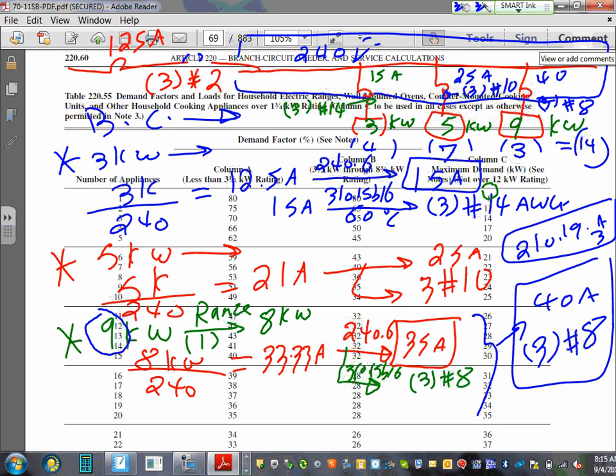60-degree column. Why 60-degree column for branch circuits? Because none of them is more than 100. But this one, I went to another table because it's a dwelling. They allow me to go to the cheaper table, smaller sizes. For branch circuits, guys, 310.15(B)(16), done. That's it. Okay, so then I came up with these two sizes.